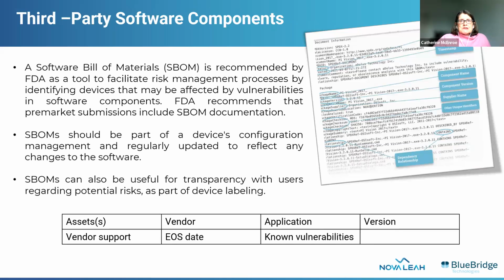So a key tool for managing your software supply chain is a comprehensive software bill of materials, and that has to be included as part of your submission. Now, the FDA asks you to submit an SBOM, but it doesn't specify a specific industry standard for SBOMs, such as CycloneDX or SPDX. But you have to consider this, that for submission, you're going to be providing evidence of safety and security risk assessment for every identified vulnerability in each software component.